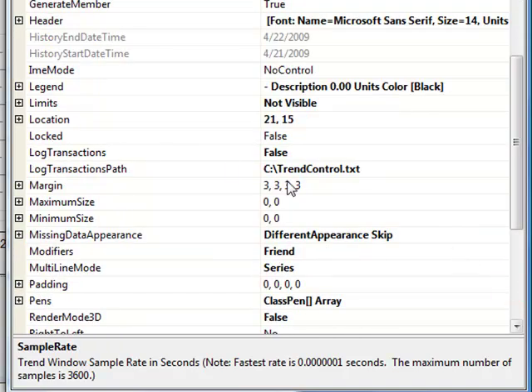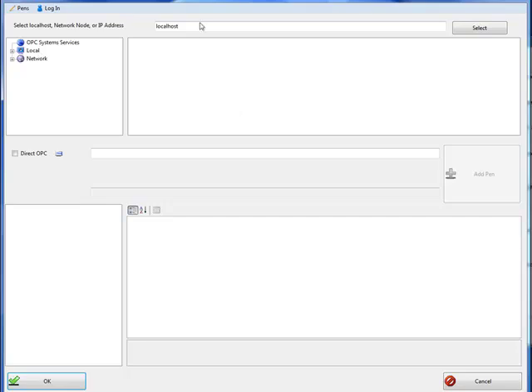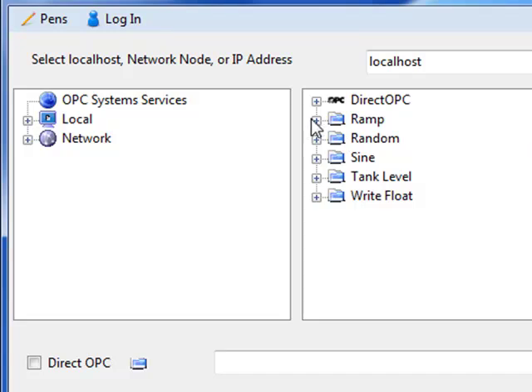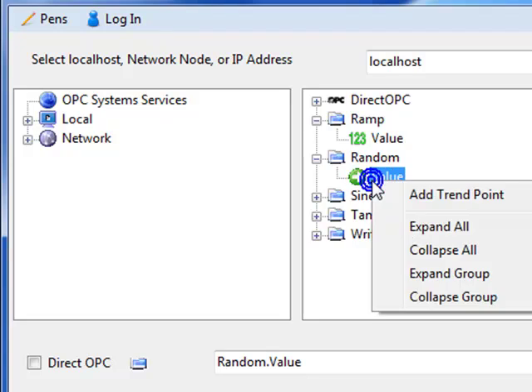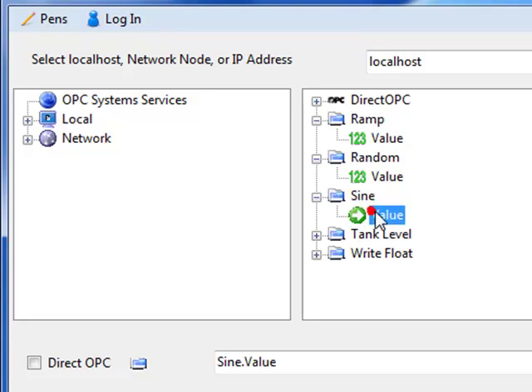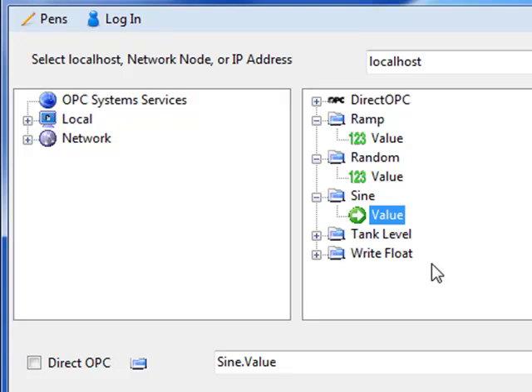Then we're ready to select the pens that we want to see in this trend window. If we select the pens property, there's a browse button that appears to the right. The pen dialog now appears, and we are ready to select the local service or even a remote service. Here's a list of tags in our default configuration. We'll select the ramp signal and add that, then the random, and you can also right-click on a parameter and click add trend point. Remember that the trend point property must be enabled under configure tags for that tag to be visible on a trend. You can also connect directly to OPC servers and bypass the opcsystems.net tags by using the direct OPC interface.